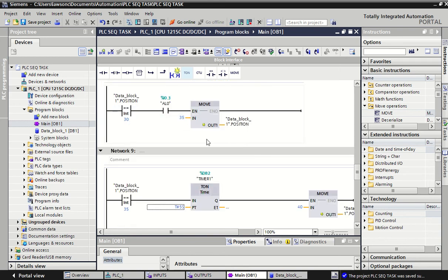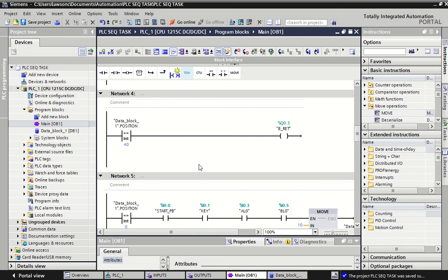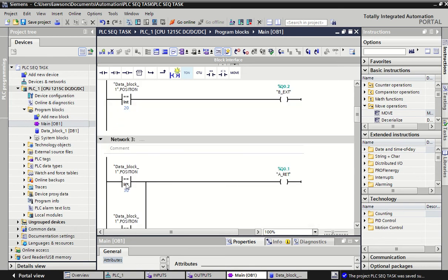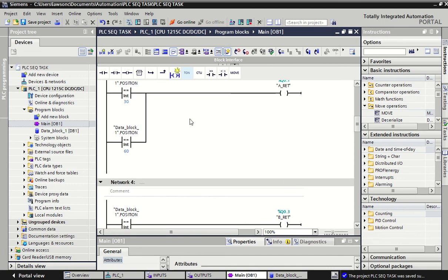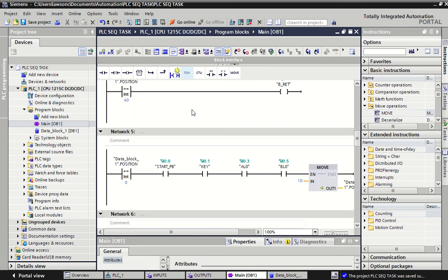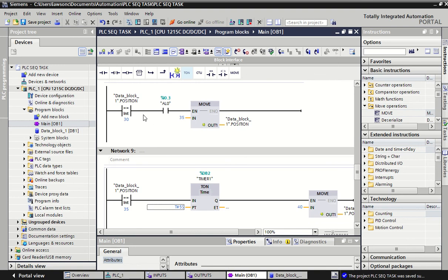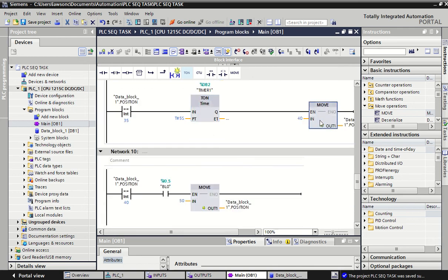And then that shows the benefit of us just giving ourselves a gap of 10, because now I don't need to change anything, because even on the outputs, step 30 makes A retract, step 40 makes B then retract, but I know in step 35 in between there, it's already added in a 5-second delay, because it has to move. Step 30 makes A retract. There we know A is retracted, goes to 35. In 35, we're going to wait for 5-second delay. Into step 40, then we can make B retract.